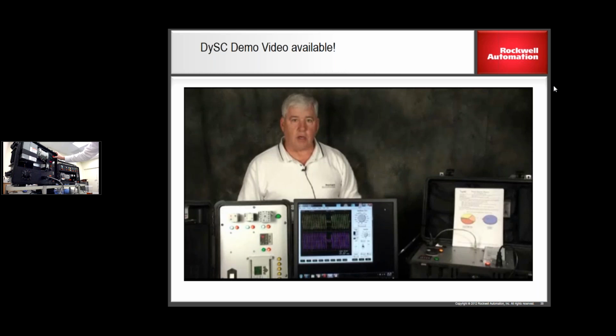I'm going to go up to a second. What was it, a second and 20 milliseconds? Got to get that in there. I should have reset that. Okay, we'll create that sag. That probably did surprise nobody. Yeah, you get bad enough, they all go down. PLC will run out, everything will just fail. All right, so I'm going to leave it set there, kind of our worst case.